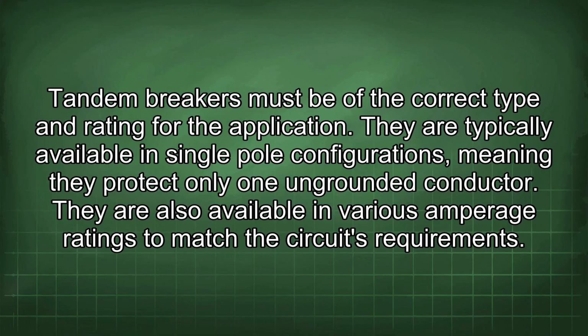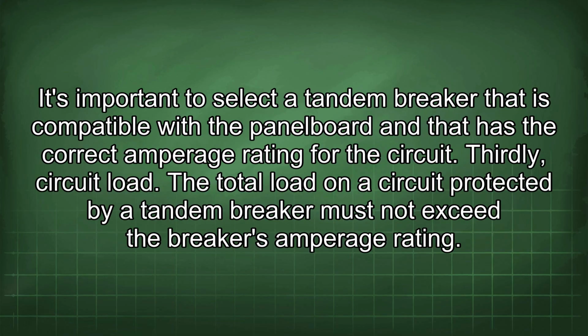They are typically available in single pole configurations, meaning they protect only one ungrounded conductor. They are also available in various amperage ratings to match the circuit's requirements. It's important to select a tandem breaker that is compatible with the panel board and that has the correct amperage rating for the circuit. Thirdly, circuit load.